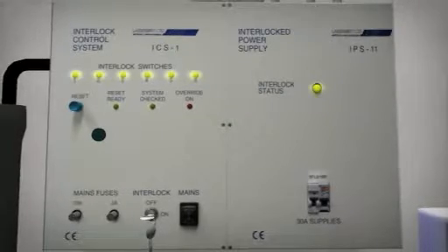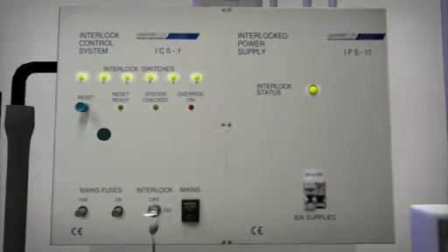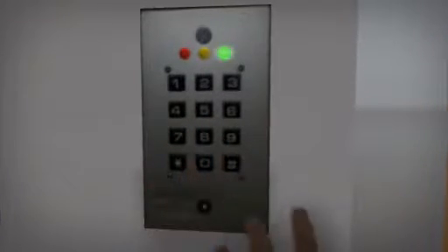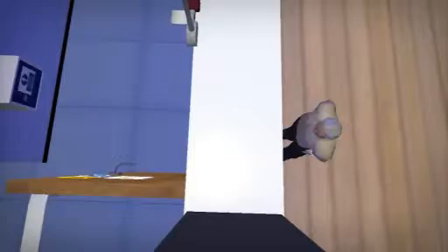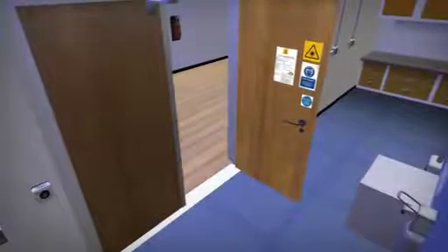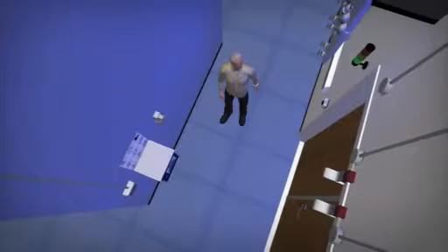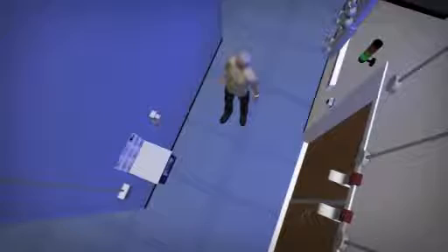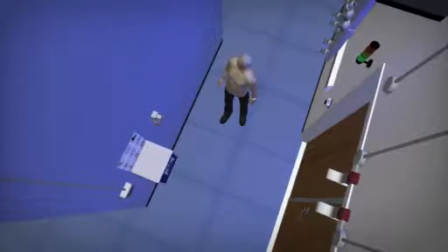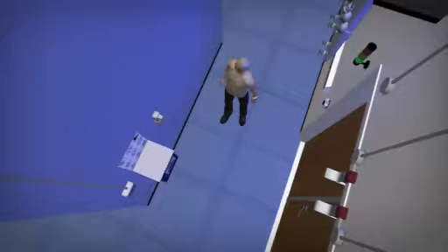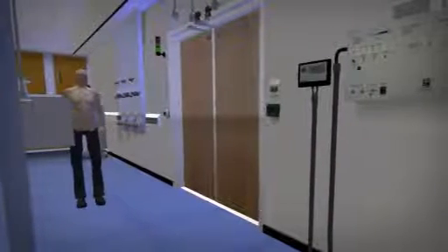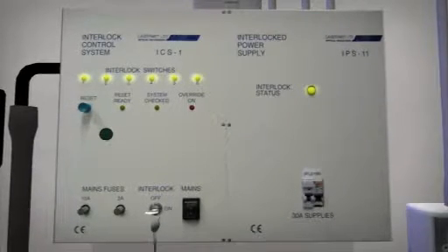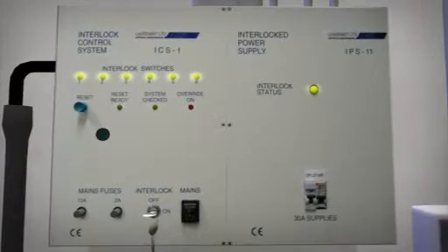The lab door is monitored by an interlock control box, which is also connected to the laser systems inside. When an access code is entered or an entry card is swiped, the door lock releases and the interlock is overridden. Immediately on entering the lab, you will often see a wall partition or screen between the door and the laser itself. This is in place to protect you from any direct exposure to possible stray beams from the laser as you enter. You can usually find the interlock control box near the entrance. From here, the entire remote interlock system can be activated, deactivated, and monitored.